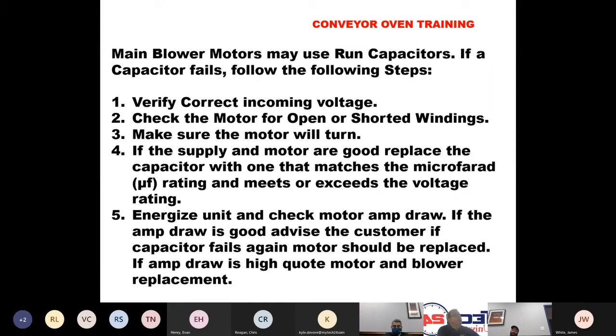Some main blowers are going to use run capacitors. If you have a run capacitor that fails, follow these steps. First, make sure that the motor incoming voltage is correct. Second, check the motor for open or shorted windings. Third, make sure the motor will turn.